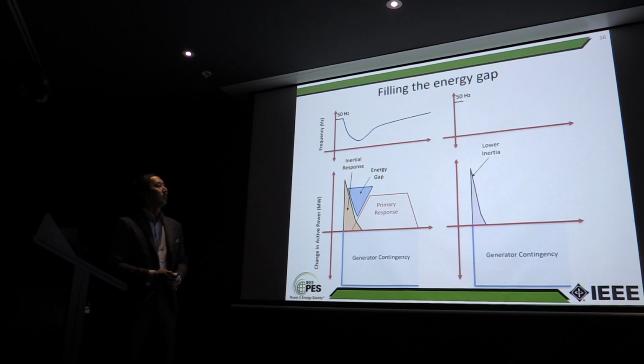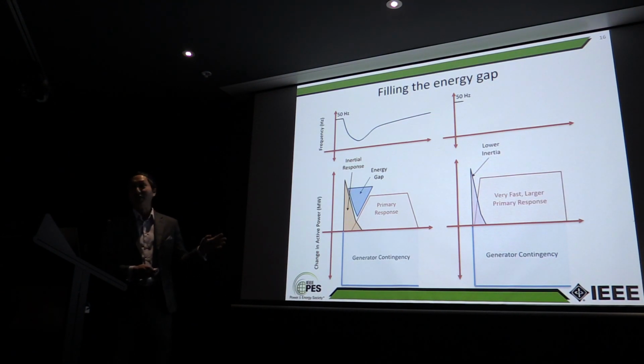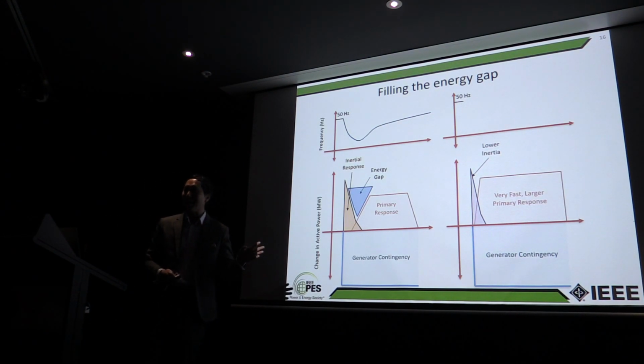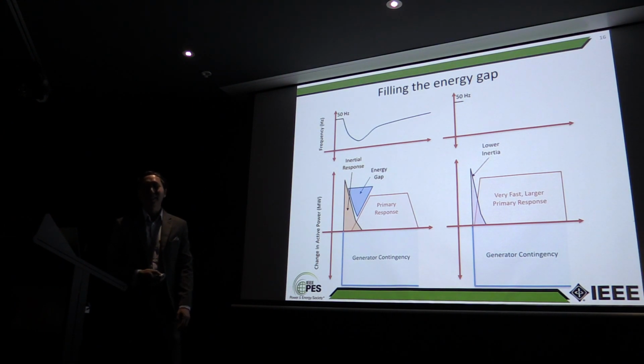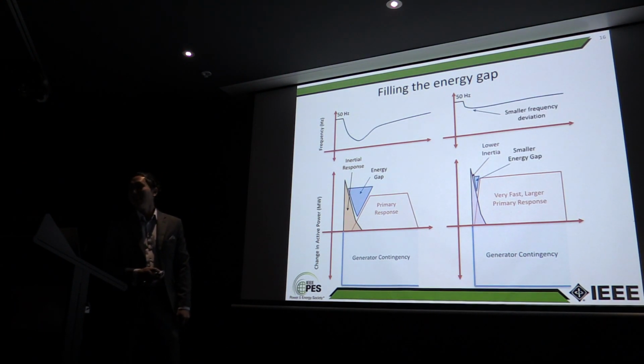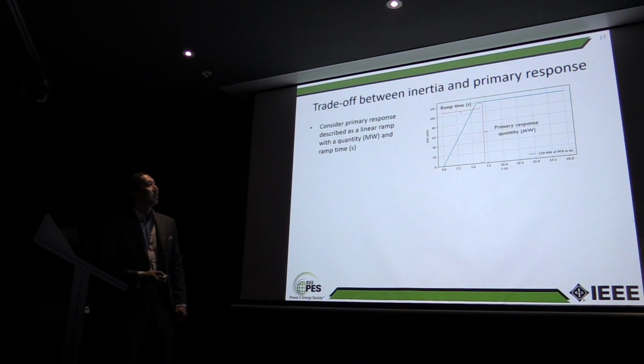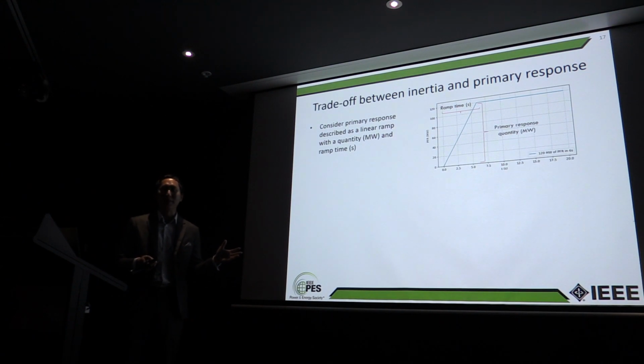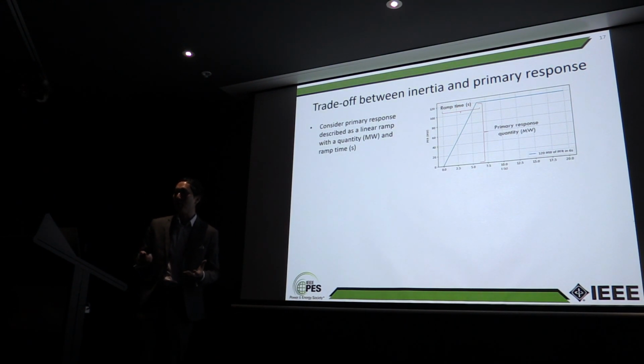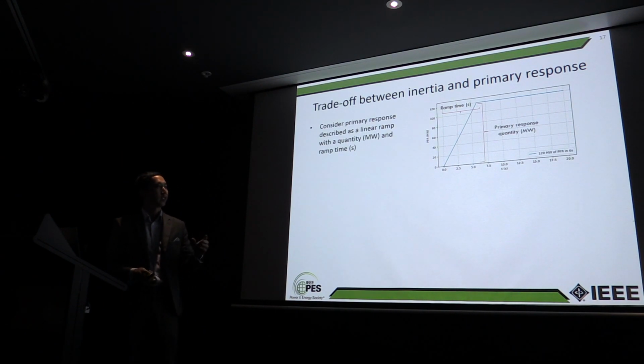So in that case then, what happens if we had the same lower inertia, but we had a really fast and a high amount of primary response? Then that gap would be pretty small, right? And so as you'd expect, frequency deviation would also be very small. So that leads me to this next point. There's actually trade-offs here between how much inertia we have in the system, the quantity of the primary response, and how fast we want to exercise that primary response.